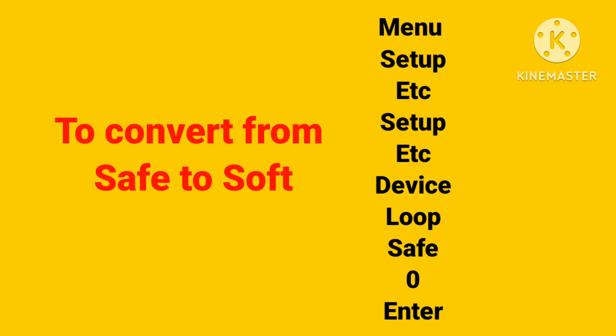If you want to convert from safe back to soft — the normal mode is called soft address — the process is the same: go to Menu → Setup → ETC → Setup → ETC → Device → Loop → then Safe, and put 0 to revert the device to a soft address.